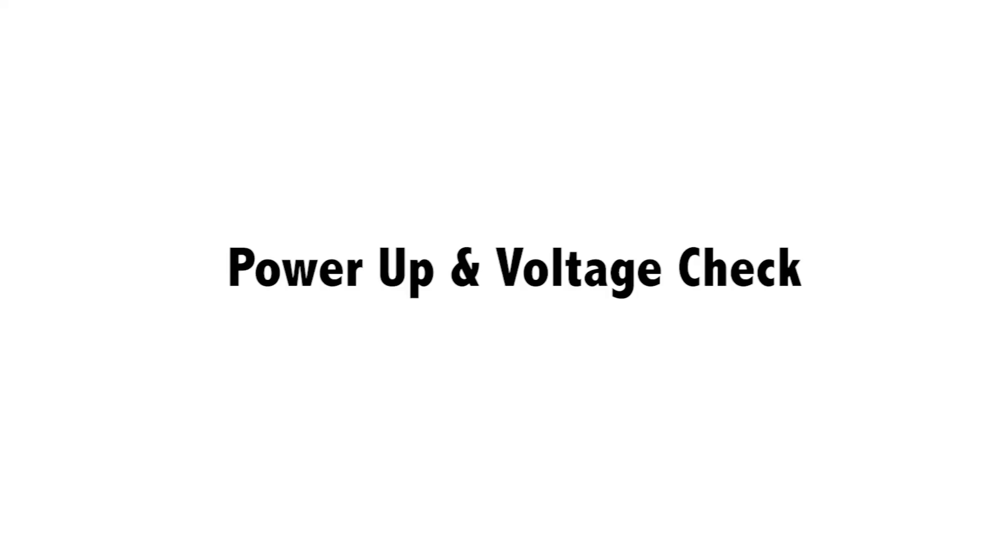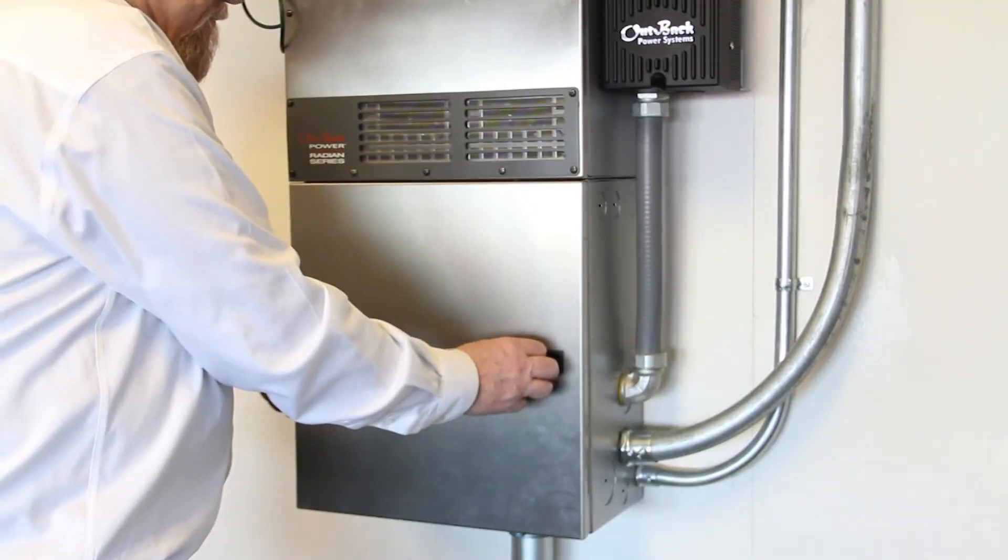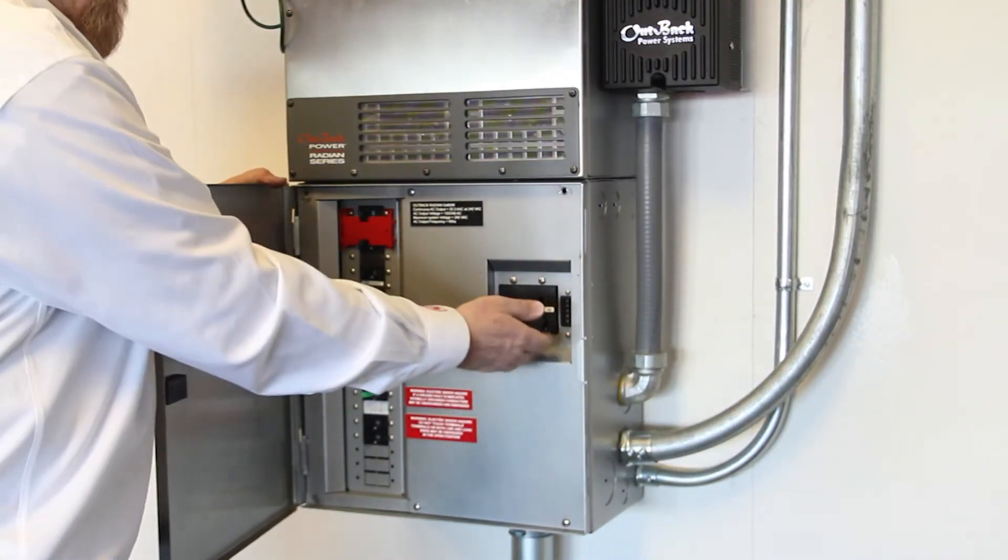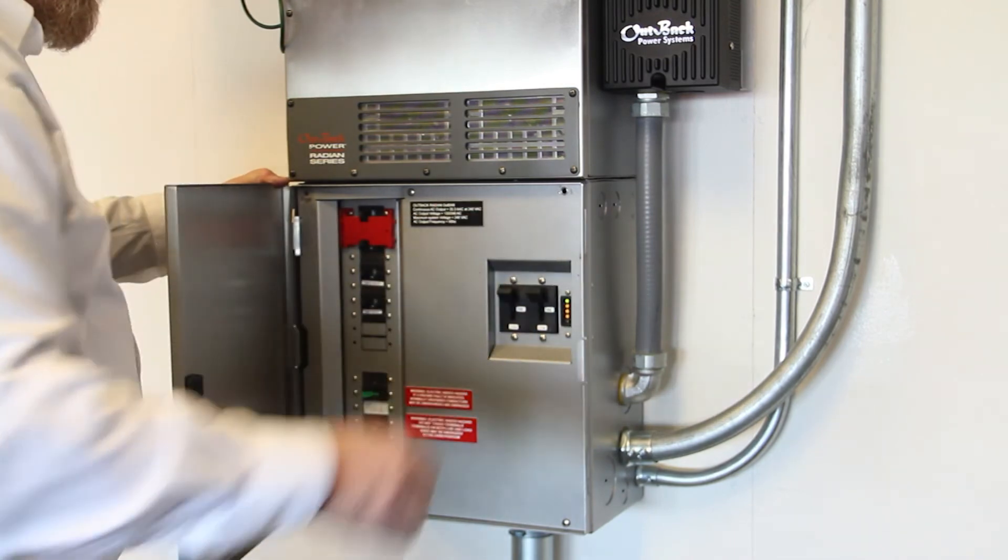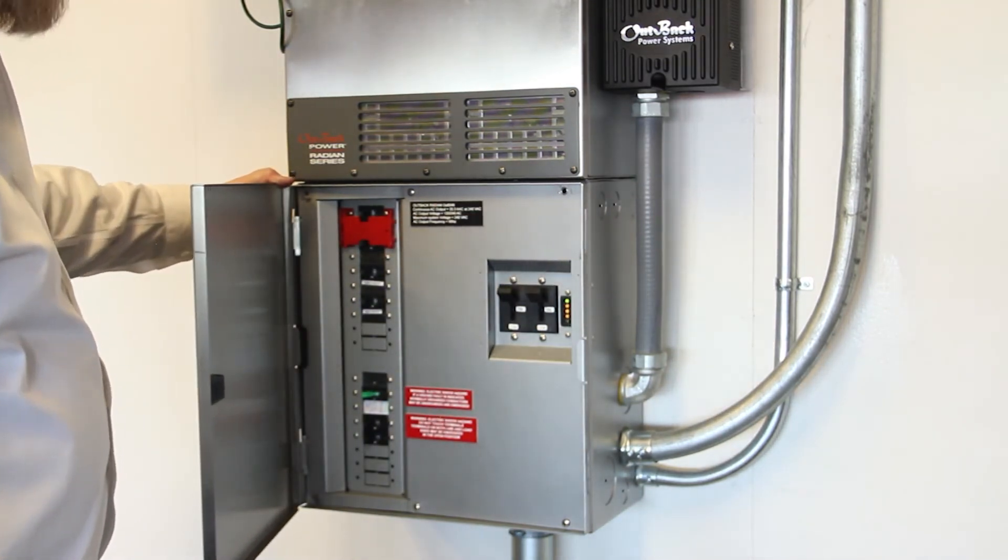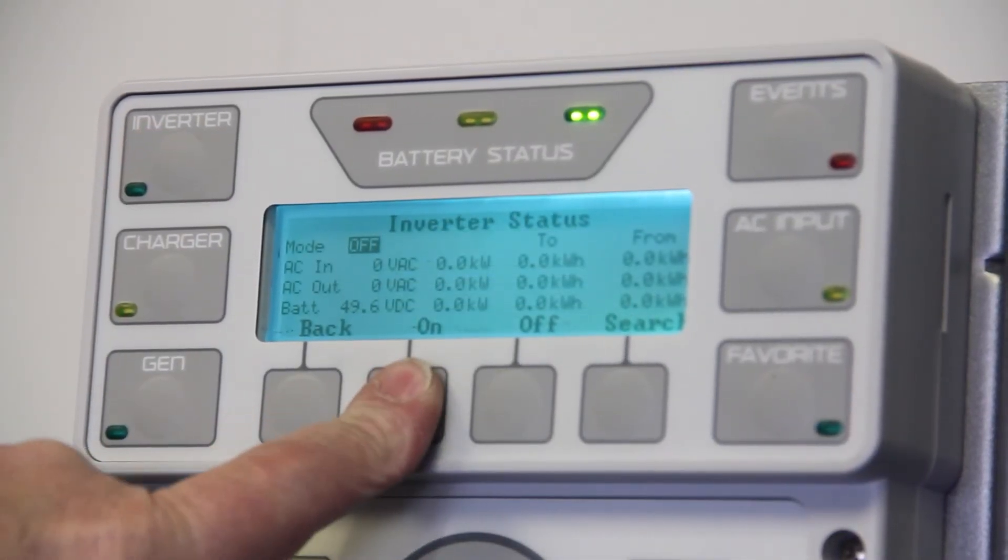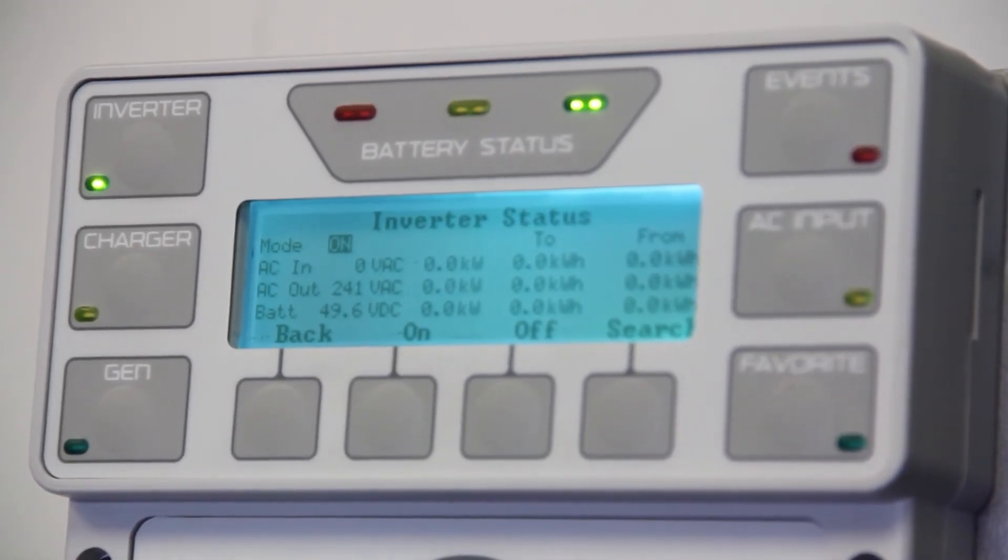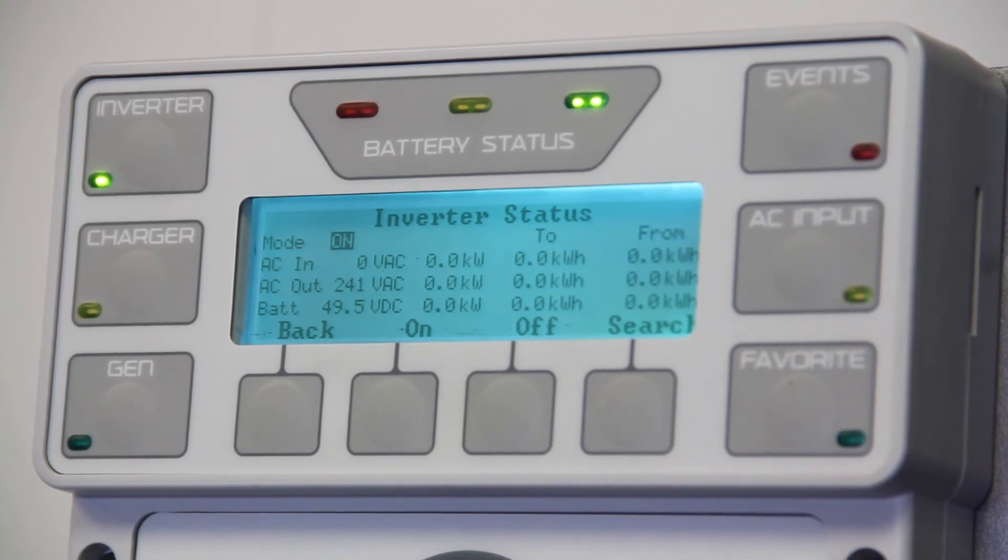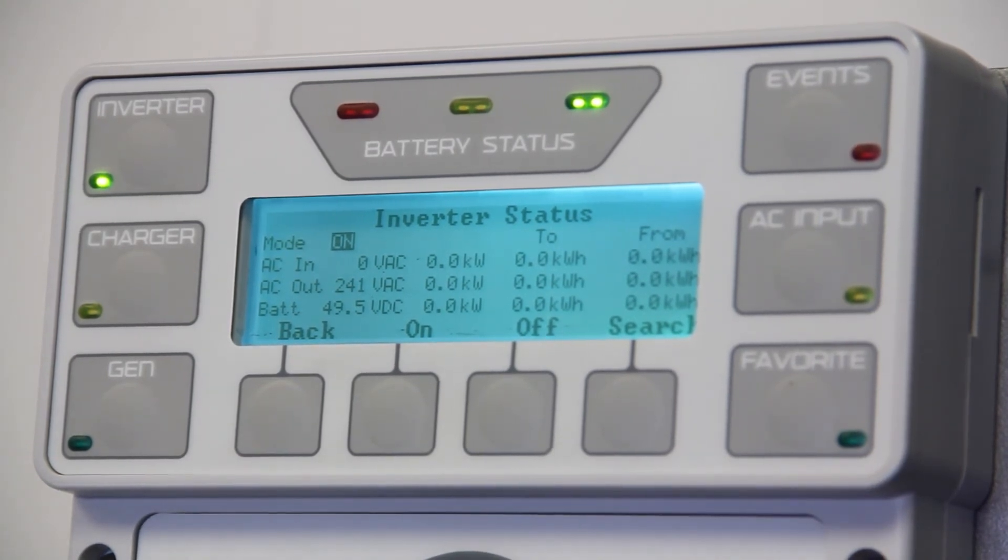Power up procedure and output voltage check. Turn power sources back on. Apply power to the inverter by turning on the DC circuit breaker. Keep AC breakers off. You will hear each fan cycle once, then both together. Once the inverter is powered up, from the Mate 3, press the inverter button, then press on. This will allow the inverter to start inverting power. Verify the output voltage reads 240 volts displayed on the Mate 3.